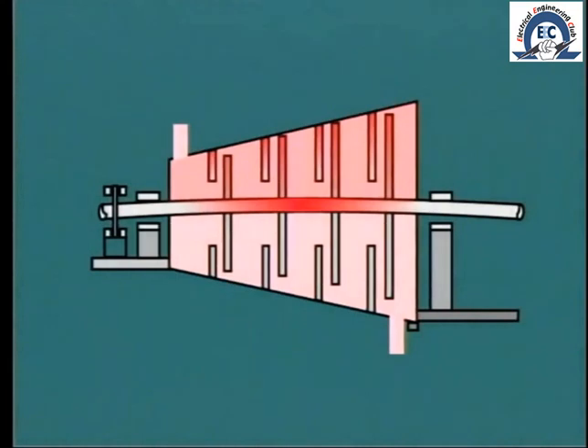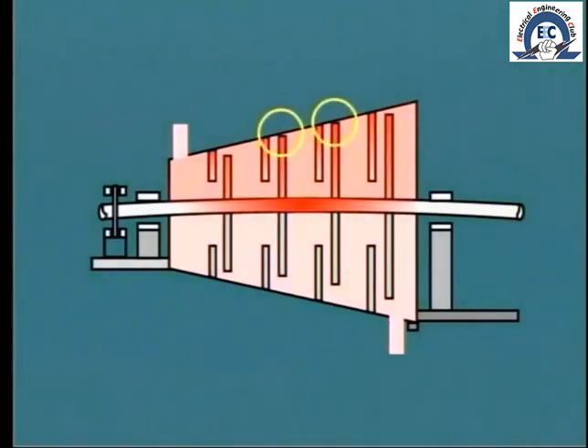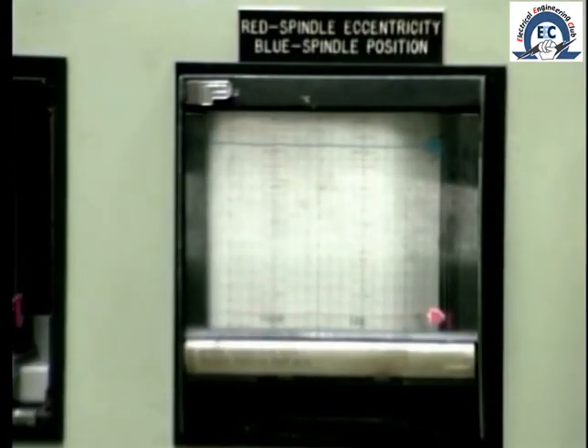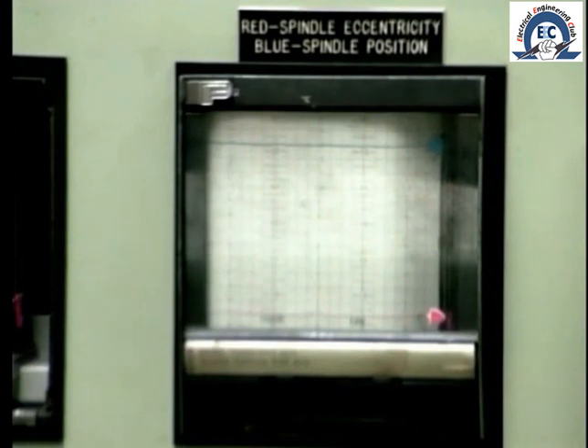When this occurs on the rotor it leads to an increase in eccentricity. The shaft and rotor take on a slight bow due to temperature distortion and this is exaggerated by the centrifugal force of rotation. Eccentricity is dangerous because it results in a reduction in radial clearance between the rotating and stationary parts. The degree of eccentricity is measured and recorded at the operator's terminal or control board.